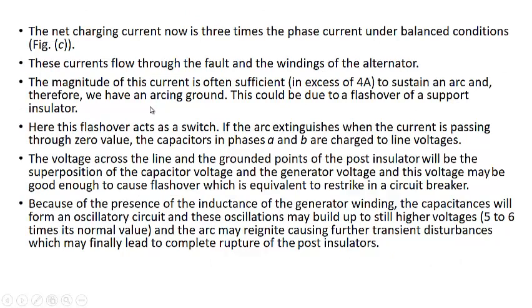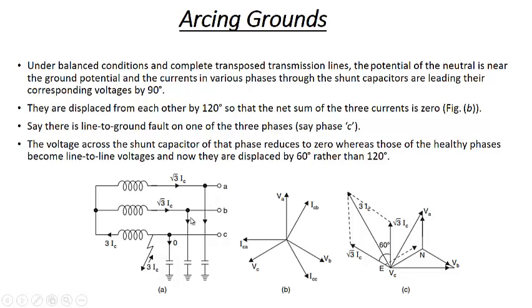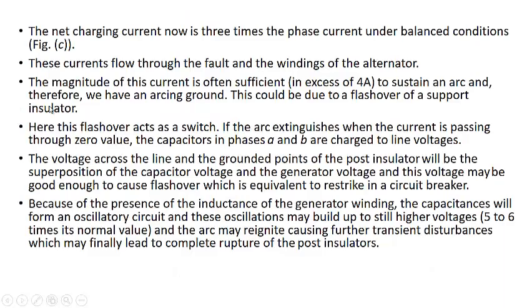Now this is very important, and this actually is the explanation of the arcing ground. The net charging current now is 3 times the phase current under balanced conditions. Now this 3 times will be in case of a single line to ground fault. So these currents will flow through the fault and through the winding of the alternator. The magnitude of this current is often sufficient, in excess of 4 amperes, maybe 5, 6 to 10 amperes, to sustain an arc.